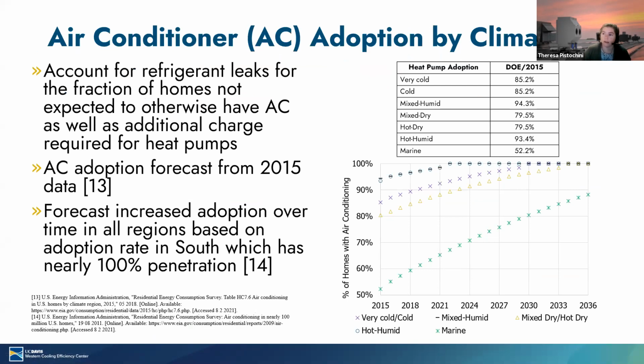Leaving CO2 emissions and talking about emissions of other gases: one issue with heat pump adoption is the concern of additional refrigerant being used beyond what is used for air conditioning today. Providing heating with heat pumps instead of furnaces increases refrigerant use in two ways. First, we have to account for all the refrigerant used in homes that do not have air conditioning. Second, we have to account for the incremental increase in refrigerant in heat pumps compared to air conditioners of the same capacity, as a result of additional components heat pumps contain, such as additional valving and possibly an accumulator.